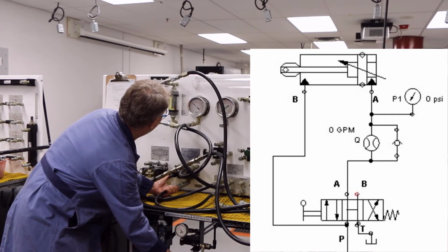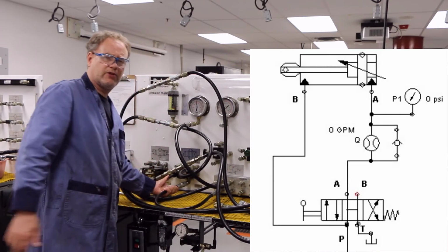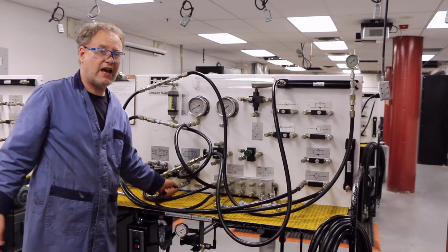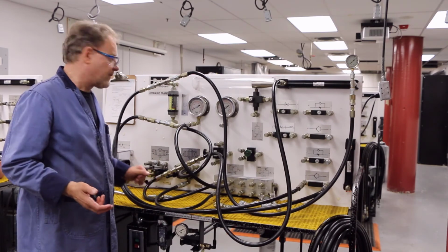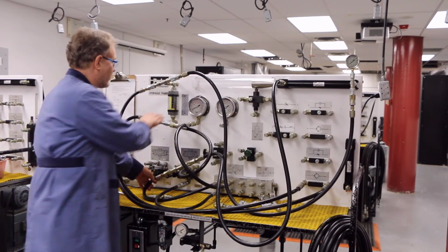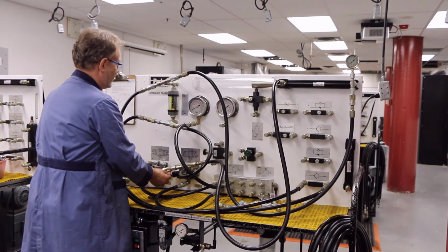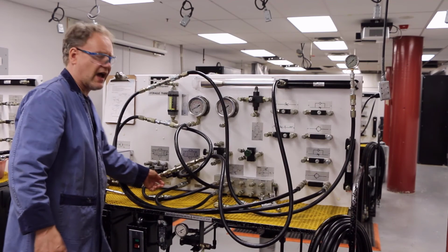Sweet. I've got 500 psi coming up. There we go. I'm at 500. I'm going to release this, and we'll see the pressure just drops because it's going to tank. That's okay. Now I have my regenerative hooked up. I've got my flow meter hooked up. I'm going to study the flow, and we're going to see it's going to jump up quite a bit. Check it out. Look at that. I'm over 4. Now I'm going to retract this.